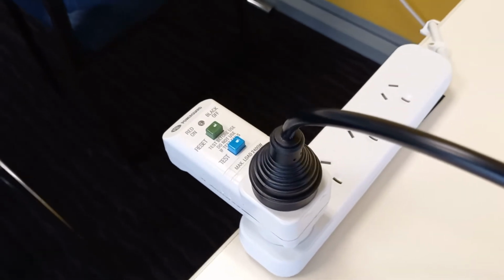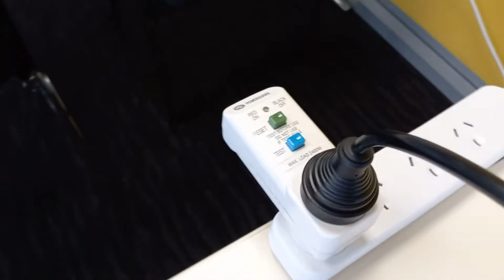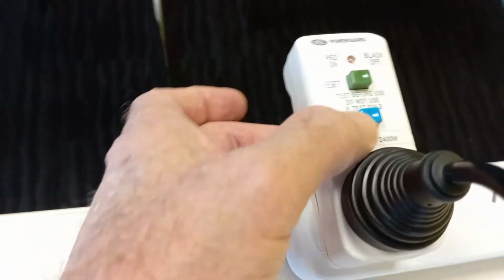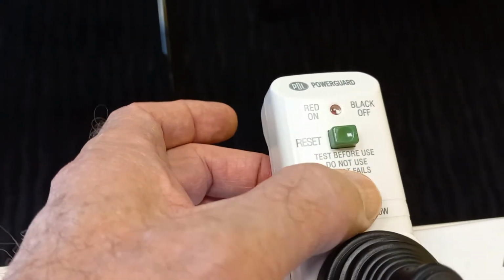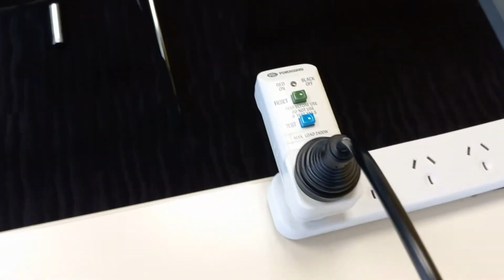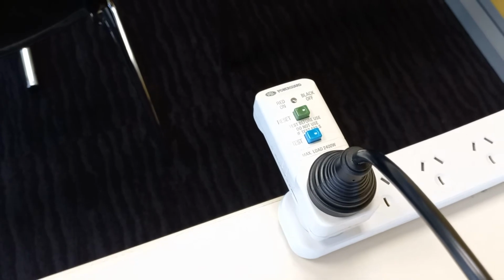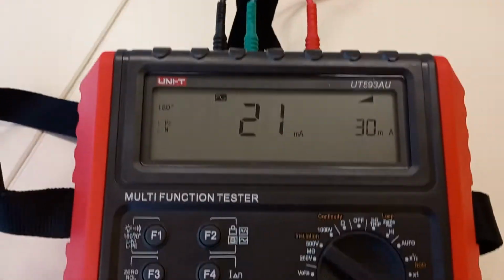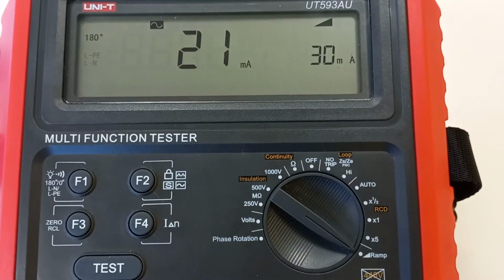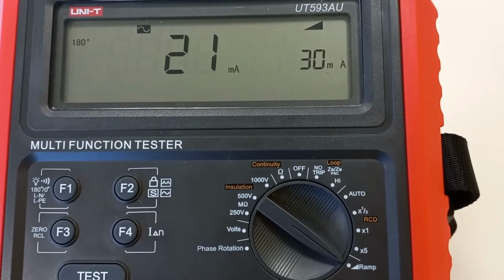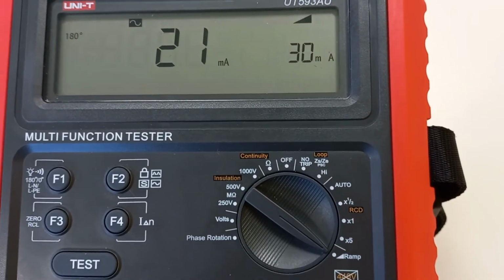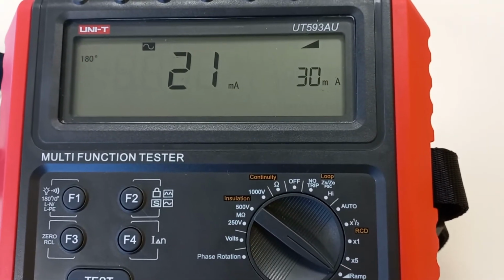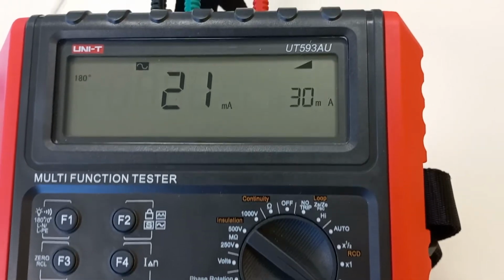We can legally just trip it by pressing the test button, that one there, and that is a legal test to check its operation. But by using the actual RCD tests, we get a lot more information on the actual operation of the RCD, which can be useful, especially to provide to a customer.